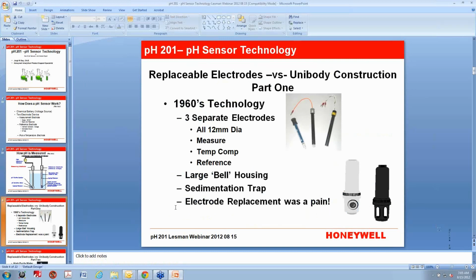Believe it or not, there's still sensors available that have replaceable electrodes. There's a variety of manufacturers that make them. What you're seeing here is a Honeywell device, a 7773. This is 1960s and going forward technology. You have 3 separate electrodes, and this was put together early on based on laboratory style sensors. They're all 12 millimeter, and you can see a picture in the top right-hand corner. The leftmost one is the measuring electrode. You can see the pH-sensitive glass on the bottom. The center one is your temperature compensator, and the right-hand one would be your reference electrode.